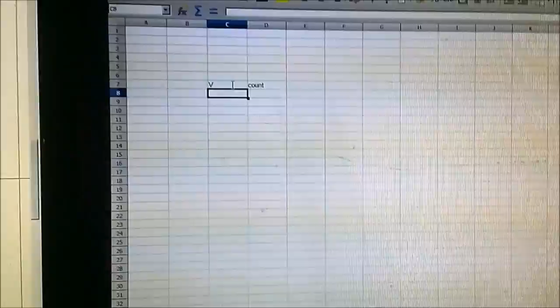Okay, so in order to calibrate, what we need is a spreadsheet up. So basically, what you want to do is you want a column with the voltage you're going to read on the meter. Try and use the most accurate meters you can find. And then you need a raw count, and so what I'm going to do right now is I'll show you the first one, then I'll go ahead and do it off camera.